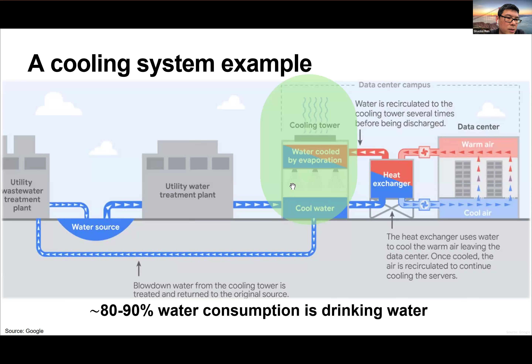Let's say we're using a cooling tower. You can see at the top, there is just constantly evaporating water. The remaining water, due to the natural evaporation process, will get cooler, and then the remaining water will be moved to the heat exchanger and further take away the heat. This process will cycle several times before the water gets too much minerals and salt, and then the remaining water will just be discharged to the wastewater processing plant, and that's considered water discharge.